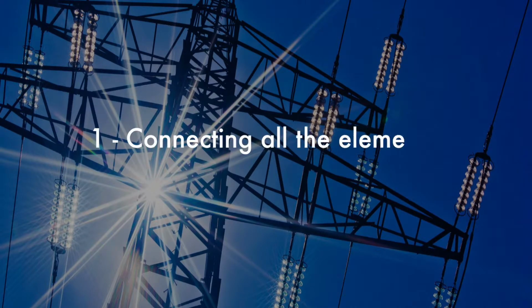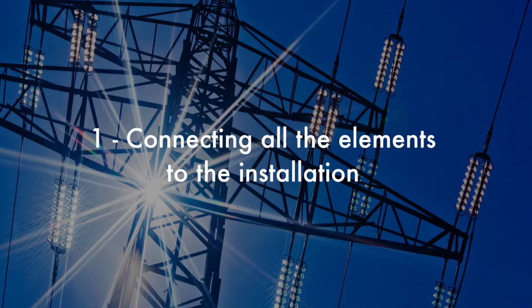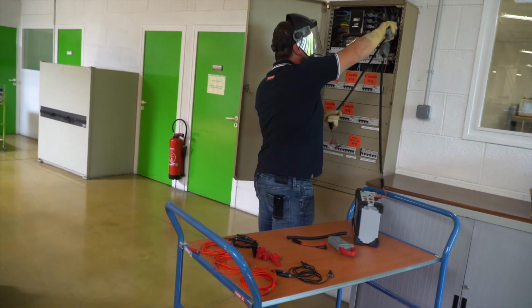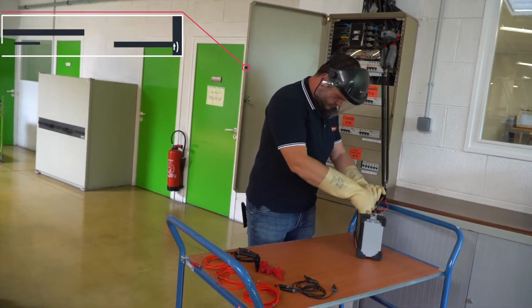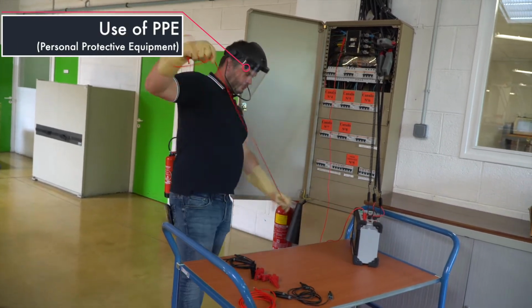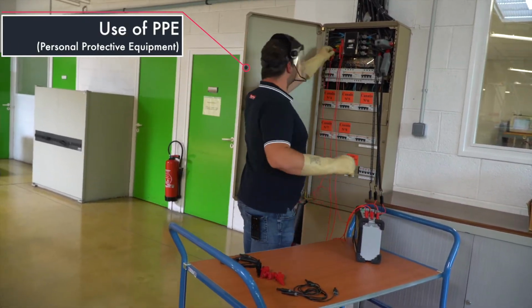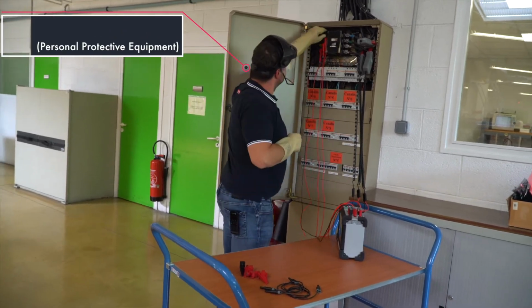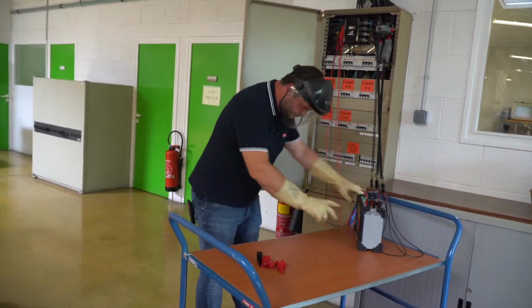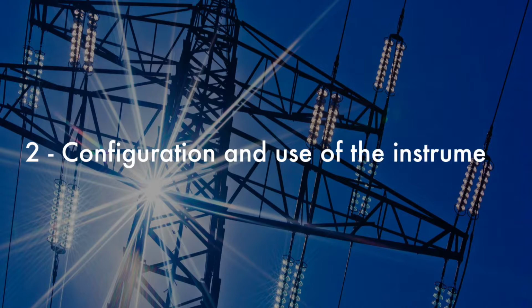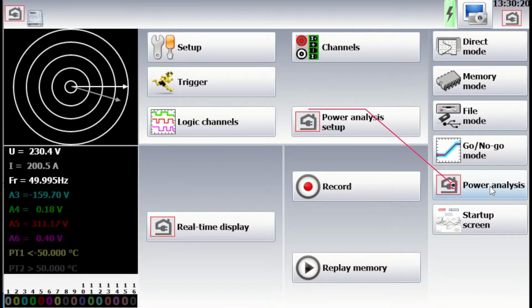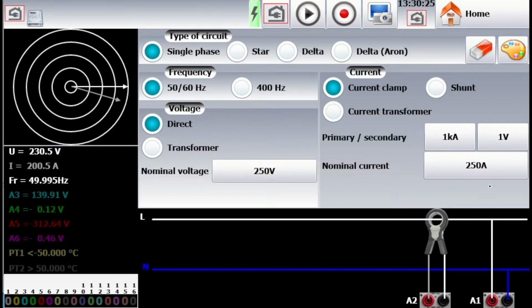First of all, let's connect the measuring leads and the current clamps to the installation to be analyzed. Now, let's move on to the instrument. First, access the Power Analysis mode by pressing Power Analysis from the home page of your instrument.